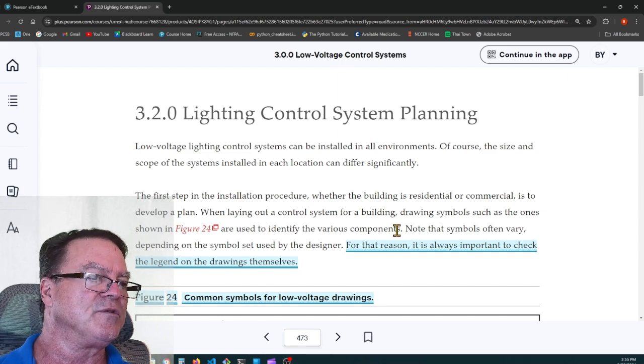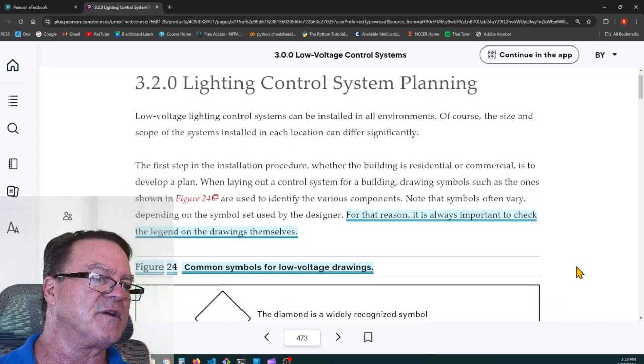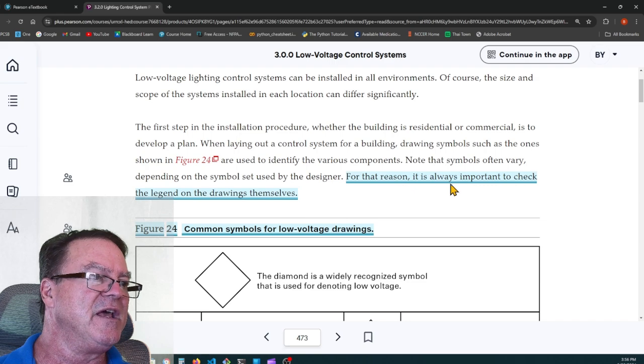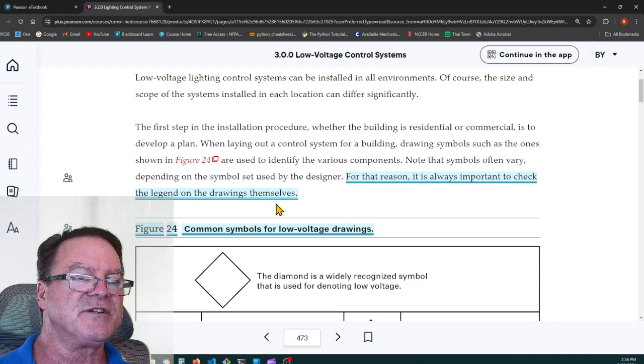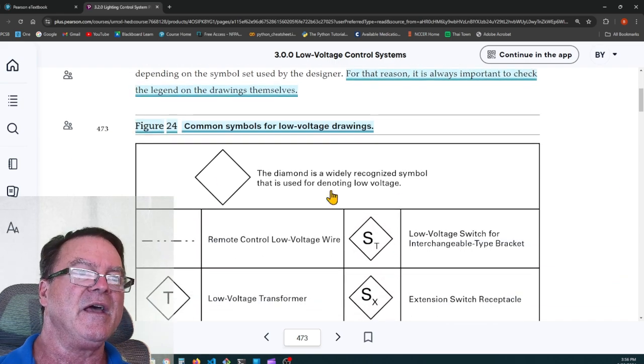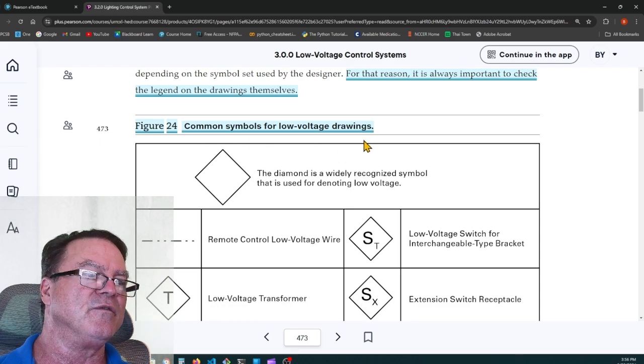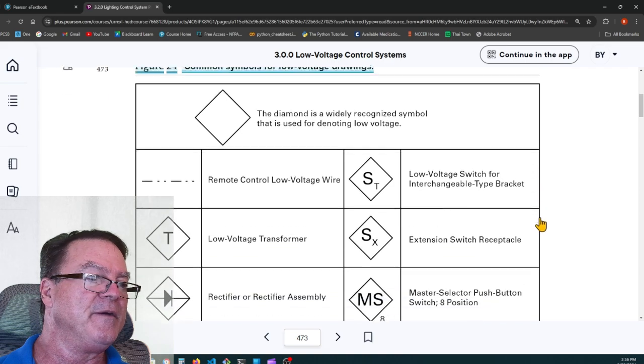When laying out a control system for a building, drawing symbols such as the ones shown in Figure 24 are used to identify the various components. Here's a highlight. It says, for that reason, it's always important to check the legend on the drawings themselves. And Figure 24 is a common symbol for low voltage drawing. Anything inside the diamond is a widely recognized symbol that is used for denoting low voltage.